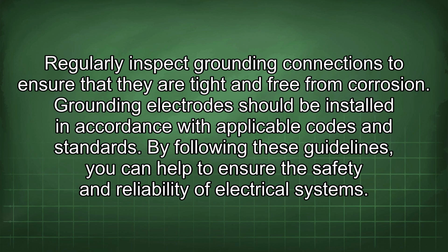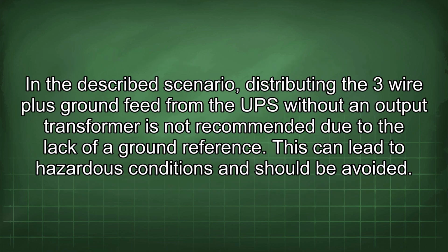Grounding electrodes should be installed in accordance with applicable codes and standards. By following these guidelines, you can help to ensure the safety and reliability of electrical systems. In the described scenario, distributing the 3-wire plus ground feed from the UPS without an output transformer is not recommended due to the lack of a ground reference. This can lead to hazardous conditions and should be avoided.